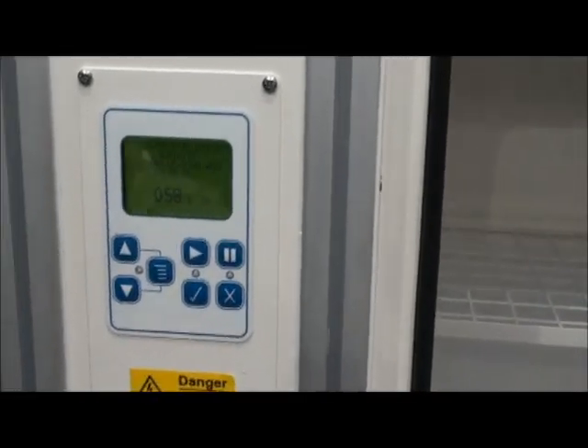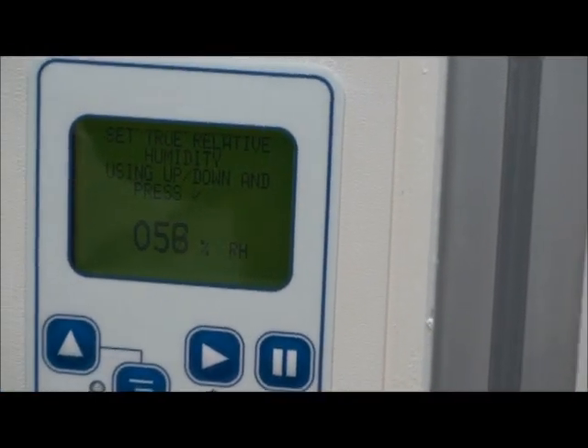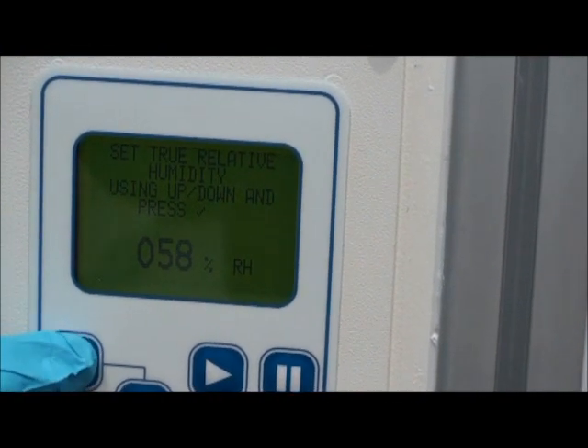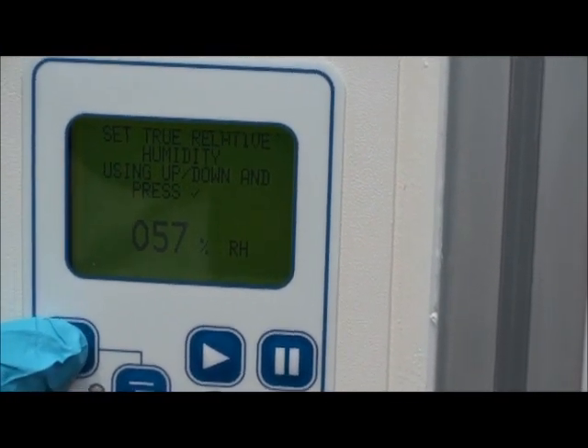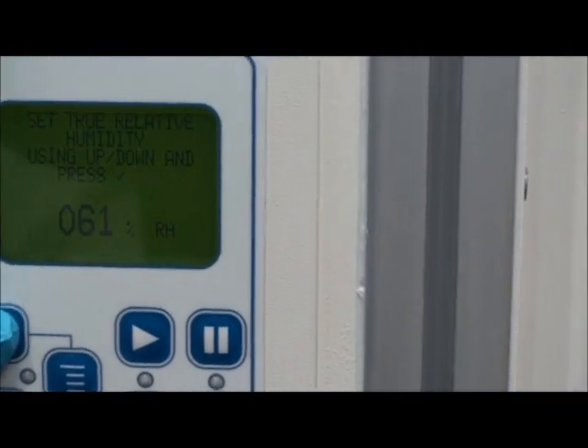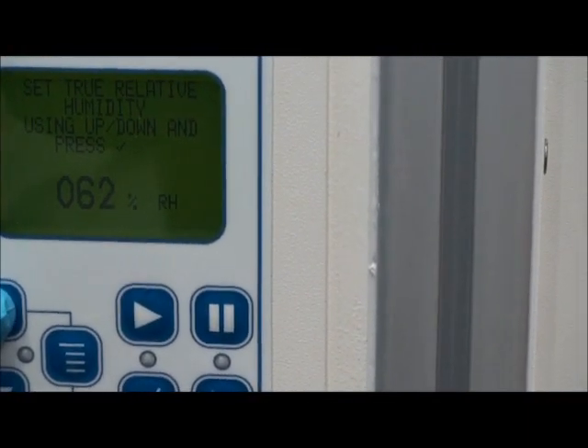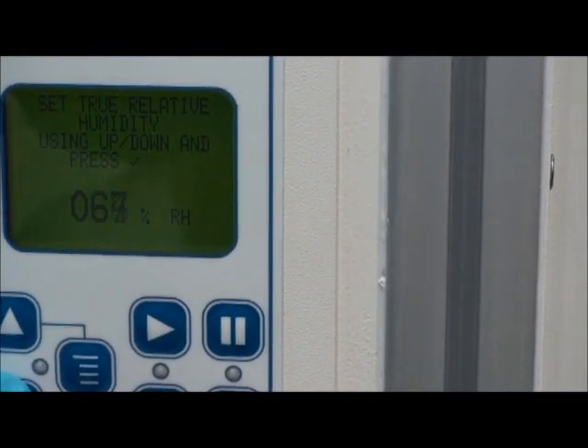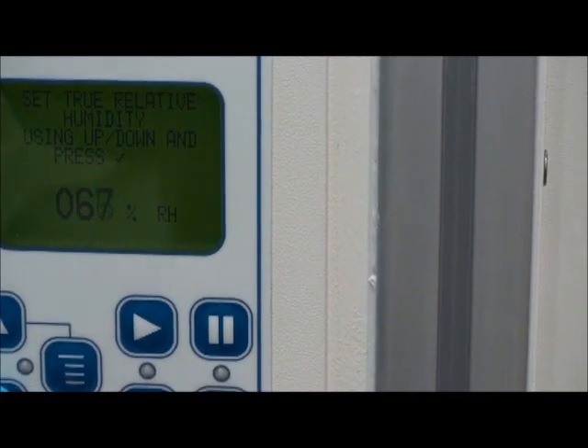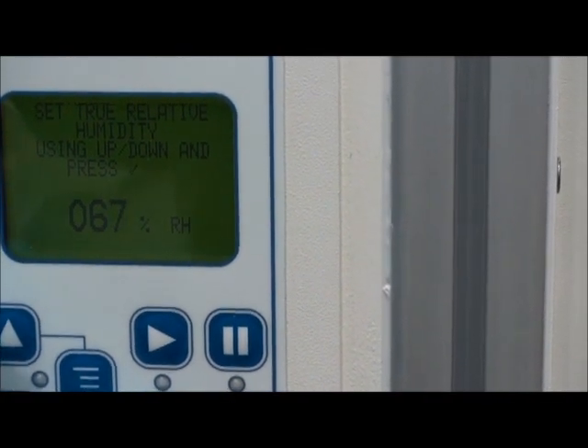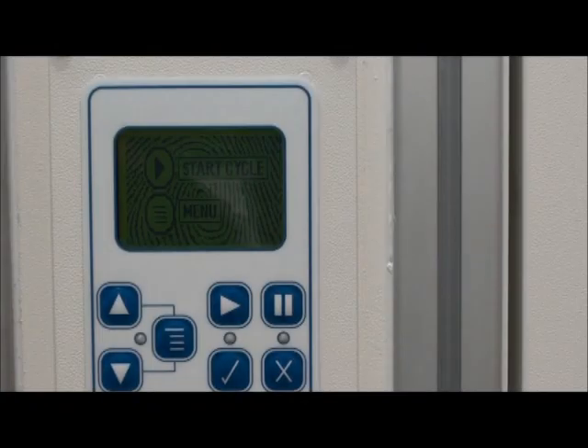So in the calibration now, we're going to press the up key to take us up to the reading that's displayed of 67. It does jump around a little bit, but as soon as you press the accept key, it reads the reading we've got. We're now ready to run the cabinet.